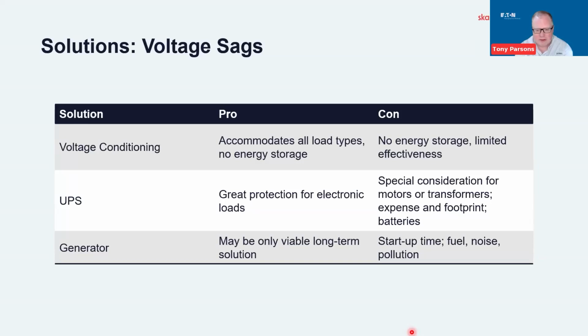So with all of the solutions, again, trying to characterize the environment in your system so that you can choose the correct one is really the best way to go. Yeah, and a big thing is understanding the source, isn't it? On one site that I had, a lot of the transformers had tap positions that were quite low, or high on the HV, low on the LV side. That had been done many moons ago for energy saving initiatives, but the load had changed on the end. Those variable frequency drives were now close to their minus 10% under voltage threshold.